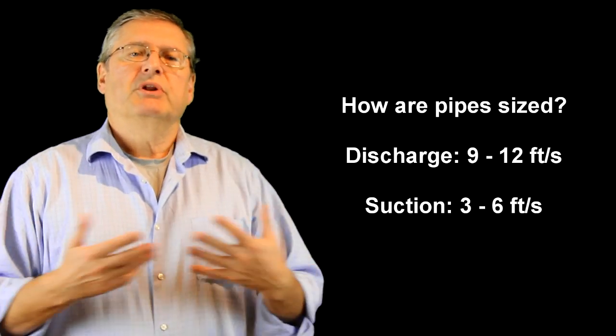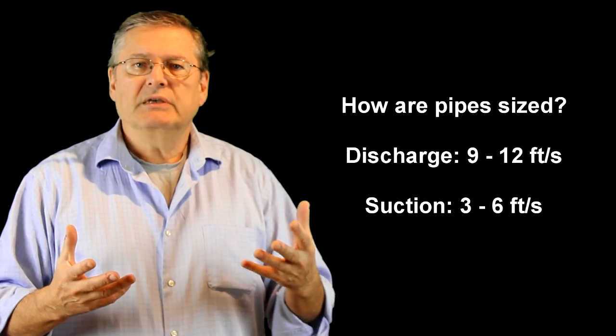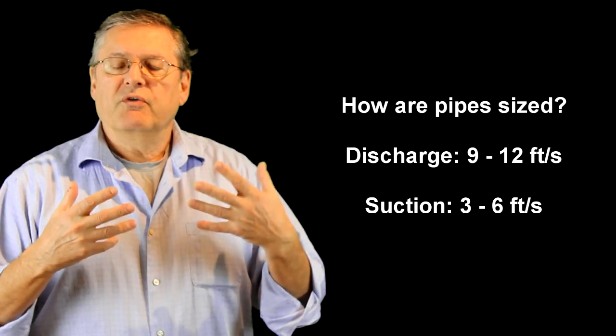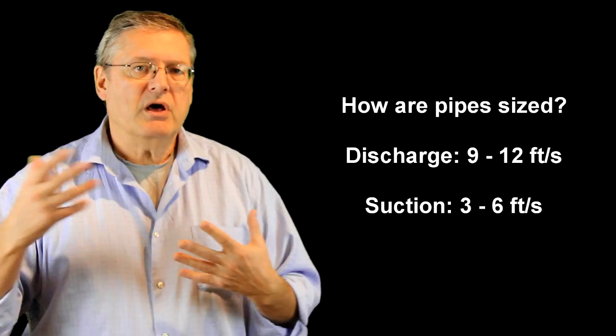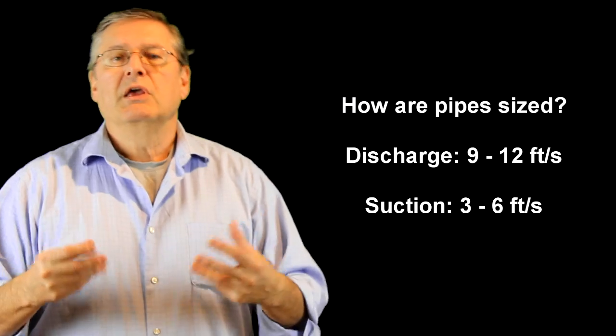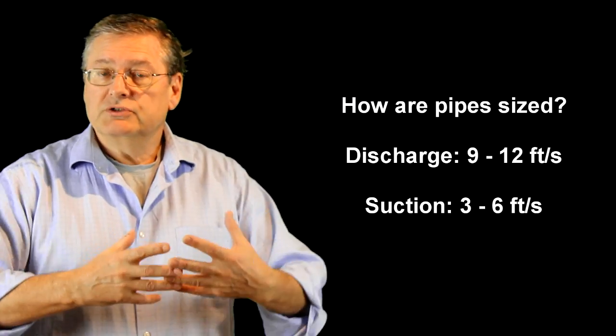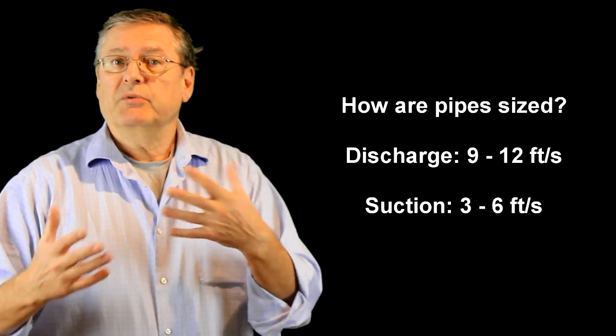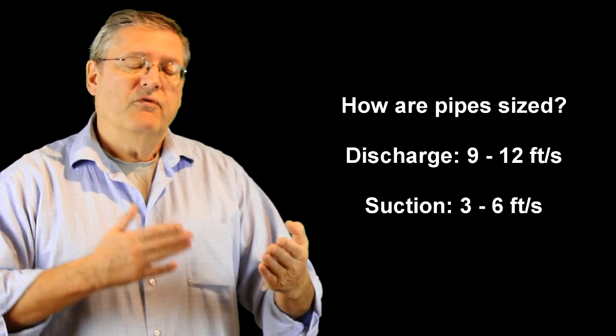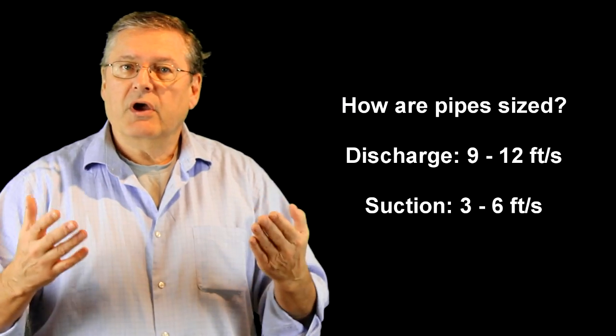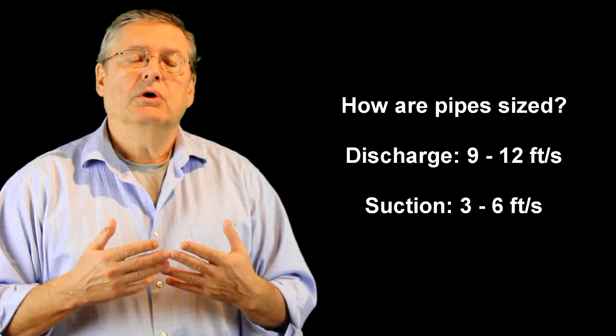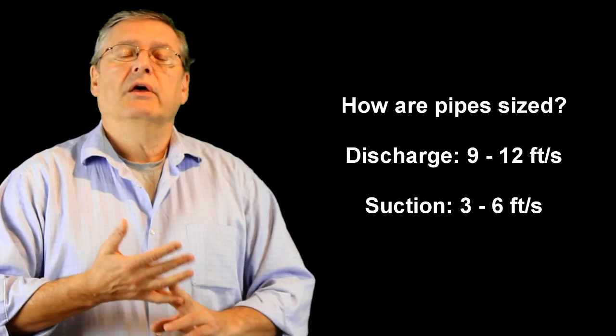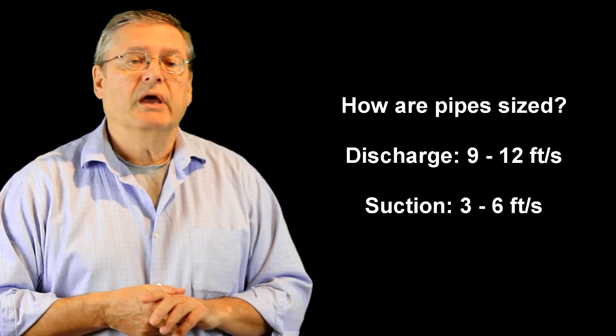Obviously somebody could do an economic analysis of the pipe size versus the amount of friction it causes. If it's very small there'll be a lot of friction and the pump will have to be bigger, which is costly. If the pipe size is very large then the power can be less, so there's a trade-off. If you have the velocity and flow rate you can figure out the diameter.